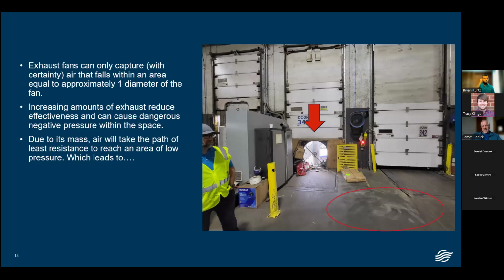Increasing amounts of exhaust. Everyone thinks, oh, I'm not quite getting the air quality I'm looking for, I must need more exhaust. And we've unfortunately probably all been in buildings that have a very, very high level of negative pressure within them, which can make the doors dangerous to be around for opening and closing. And again, due to its mass, air is going to take the path of least resistance to reach an area of low pressure, which means it's going to short circuit, which is illustrated in my next slide.